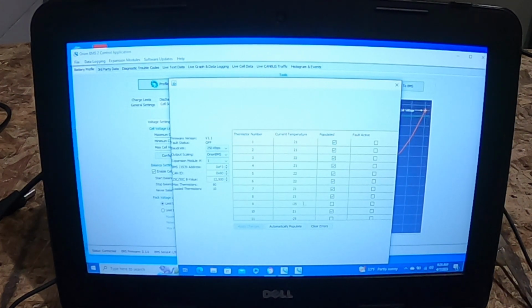The one thing I have is a bad thermistor on cell number 9, thermistor number 9 is open. I've watched videos where people couldn't get their chargers to work, and this might be the issue: an open thermistor or a wire not making contact will show minus 25 degrees, which is out of range. The profile wizard only allows charging from 0 to 25 degrees centigrade, so anything below that won't charge, and the charger won't come on. In my case it was a bad thermistor or bad wire connection, which I'll troubleshoot later.